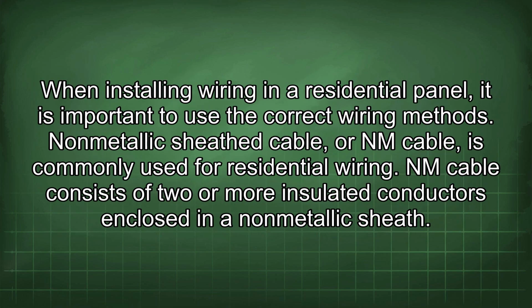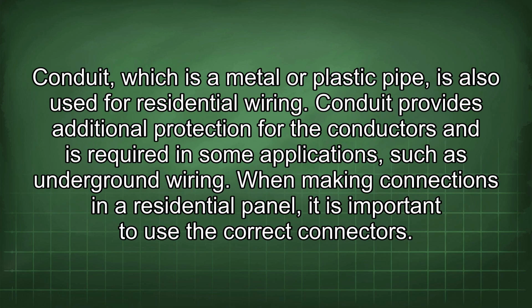When installing wiring in a residential panel, it is important to use the correct wiring methods. Non-metallic sheath cable, or NM cable, is commonly used for residential wiring. NM cable consists of 2 or more insulated conductors enclosed in a non-metallic sheath. Conduit, which is a metal or plastic pipe, is also used for residential wiring. Conduit provides additional protection for the conductors and is required in some applications, such as underground wiring.